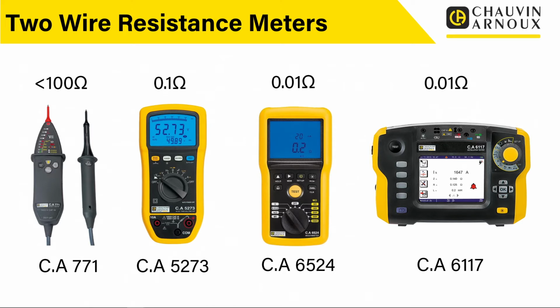Now, one that sometimes people get confused with, and we get questions about this, is why can't I use my multimeter? It's got an ohms range. Why can't I use my multimeter for measuring low resistances? And you can, but down to about 0.1 of an ohm. That's about the limit of the accuracy with a multimeter. So we generally can't get low enough to actually learn a great deal about the connections. We can see that it's a low value, but it's not really enough to give us the level of information we need to say that a connection is tight or something like that, which we would do with a micro-ohm meter.